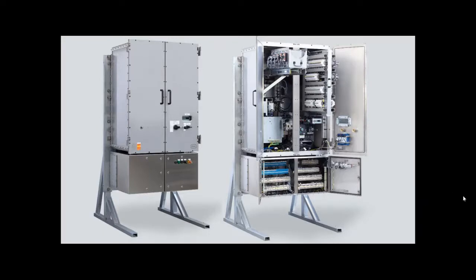And there is also the possibility to give an electrical signal if the rupture disc has opened. So like an EXP panel, if you lose pressurization, you can have a signal back to your central control room. Same thing can happen for this cabinet. That option is there, so your operators would know instantaneously if there is a problem. Now, with a typical EXD enclosure, if there's an explosion inside but nothing turns off, you do not have instantaneous awareness of that happening. So with EXP and ExPressure, you can have that option.